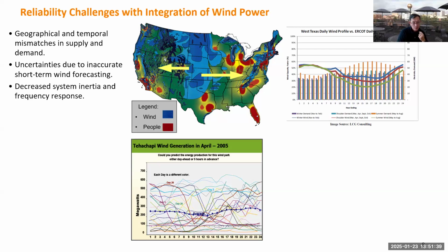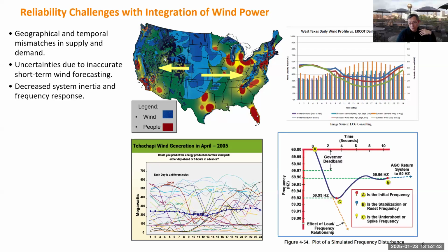The number three concern is the decrease of system inertia and frequency response. If you retire a coal-fired power plant, say 500 megawatts, because those are pretty dirty and you want clean energy, and replace it with a wind farm which can generate 500 megawatts, even if we are talking about one city in a wind-rich area, we don't need long-distance power delivery from this wind farm to the user. We can just use the power locally. And in that area we also have very good energy storage, so we have no concern for the second concern. And for the third, we have very good forecasting. But you still have another concern which can cause some reliability violation, which is the frequency response.